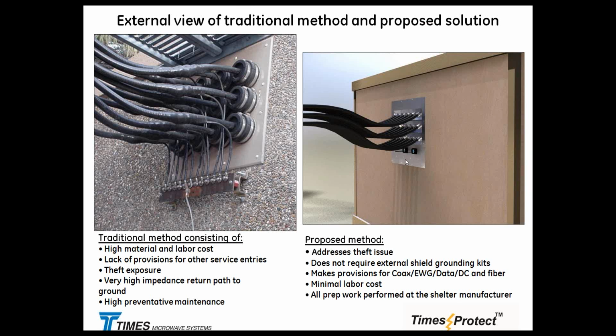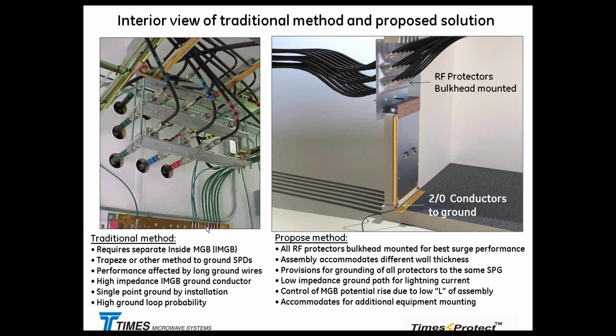And you might be asking, Bogey, where is the master ground on the outside? Well, you don't have it on the outside. Why encourage somebody to steal it if we have other better options for grounding? And if you take a look at the traditional method, trapeze with all the protectors mounted on it, internal master ground bar right here, and another piece of ground wire going to the ring ground around the shelter.